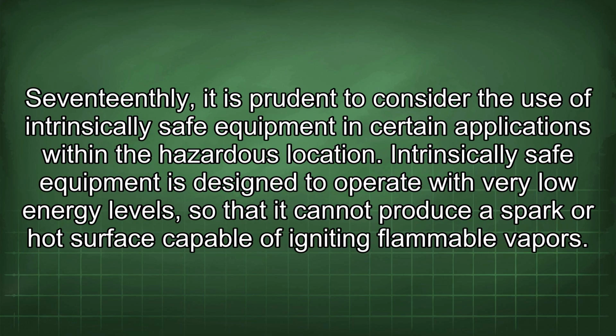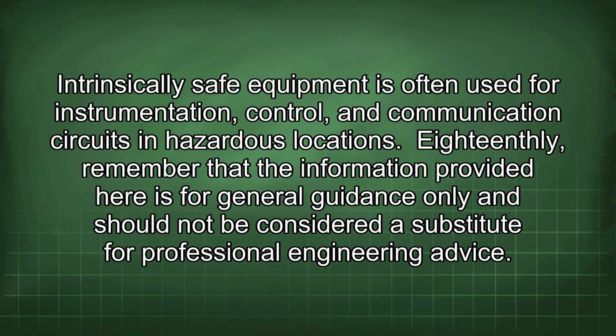17thly, it is prudent to consider the use of intrinsically safe equipment in certain applications within the hazardous location. Intrinsically safe equipment is designed to operate with very low energy levels, so that it cannot produce a spark or hot surface capable of igniting flammable vapors. Intrinsically safe equipment is often used for instrumentation, control, and communication circuits in hazardous locations.